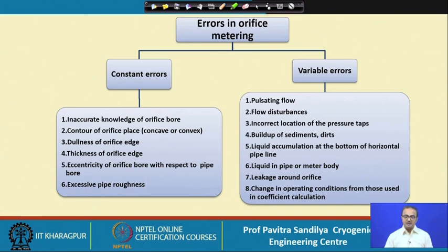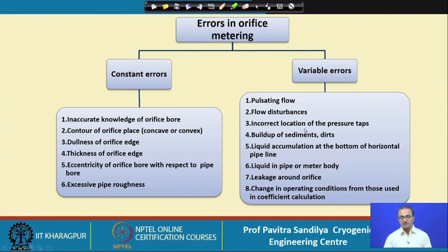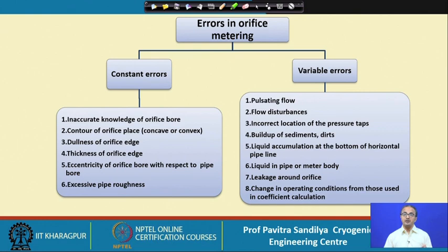There are many errors in measuring we should be aware of. Constant errors include inaccurate knowledge of the orifice bore, improper contour of the orifice (concave or convex), dullness of the orifice edge, its thickness, eccentricity of the orifice, and excessive pipe roughness. Variable errors include pulsating flow, flow disturbances, improperly located pressure taps, deposition of sediments and dirt over time, liquid accumulation due to condensation in horizontal pipes, liquid in the metering devices, leakage around the orifice, and changes in operating conditions from the base conditions used to derive the coefficient values.